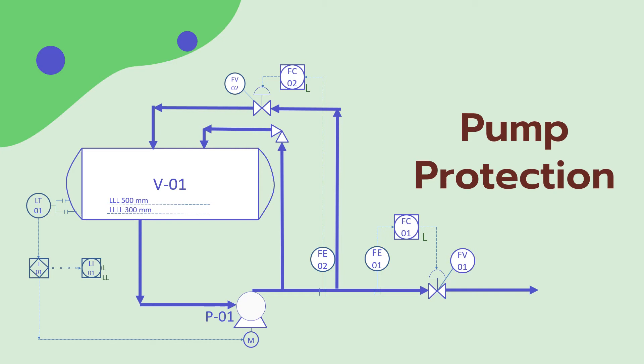There are other protections related to high motor vibration or current, or other considerations recommended by the pump manufacturer. It's important to note that if we are controlling the flow using a flow element and shall protect the pump from low flow, we shall need another flow element to send the signal to the emergency shutdown system. These should be two segregated systems to avoid common cause failure of the same flow element, which would paralyse both the control and protection of the pump. This is a general concept that applies to any equipment protection. In addition, we should make sure that no vapor shall enter the pump — one of the causes is through pockets in the suction line. Here in the P&ID, we will just write on the suction line: 'do not pocket'.